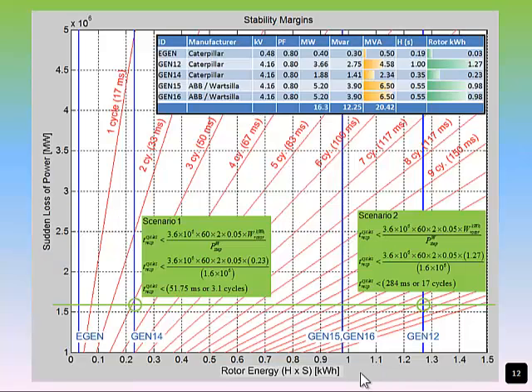Here are the response time predictions for both scenarios. We used the equation in slide five to produce this chart. The x-axis represents the diesel generators rotor kinetic energy. The y-axis represents the power lost at once or power stepped onto the generator rotor due to a contingency. The red traces represent the critical time the remedial action has to respond in order to maintain frequency. The underlying assumption here is that the sum of remedial power plus the spinning reserve exceeds the power stepped on at once.